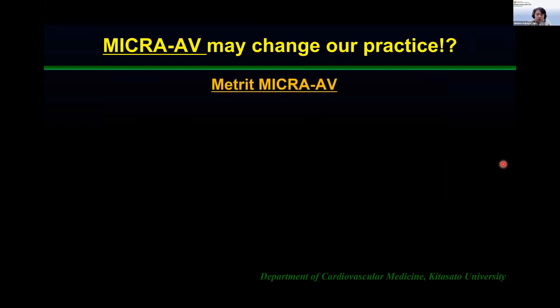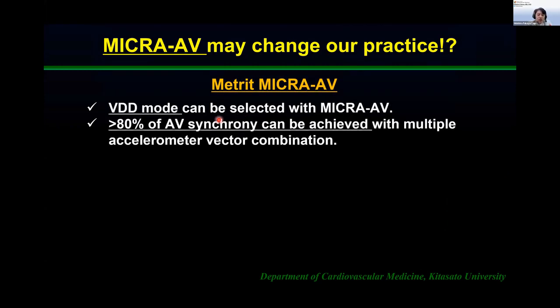So the merit of Micra AV is that we can choose the VDD mode. With this system, over 80% synchronous pacing can be achieved using multiple accelerometers on the device itself. However, we can still have some problems with this Micra system.